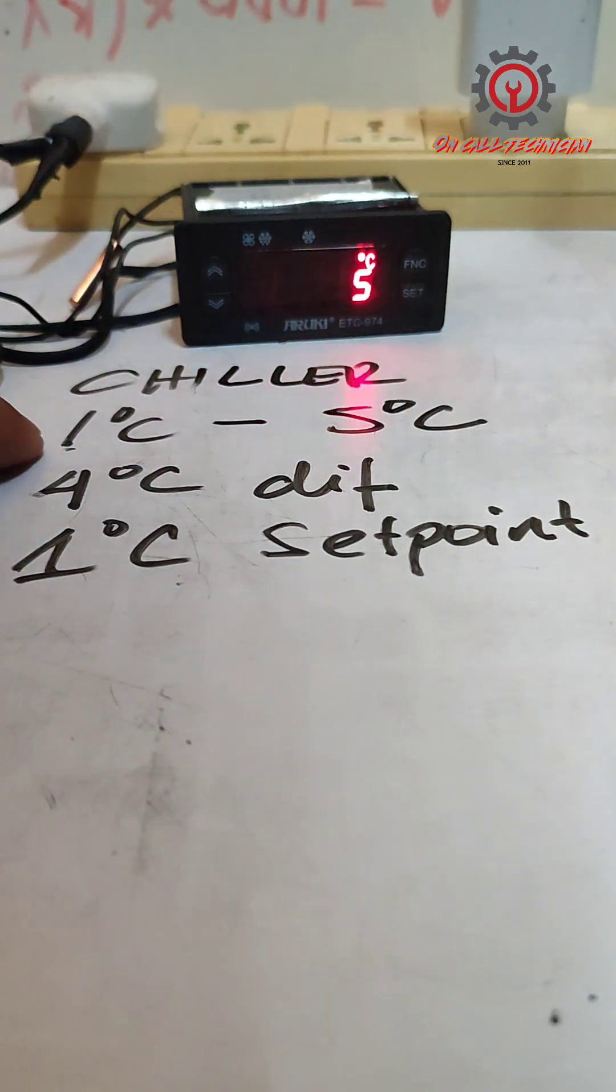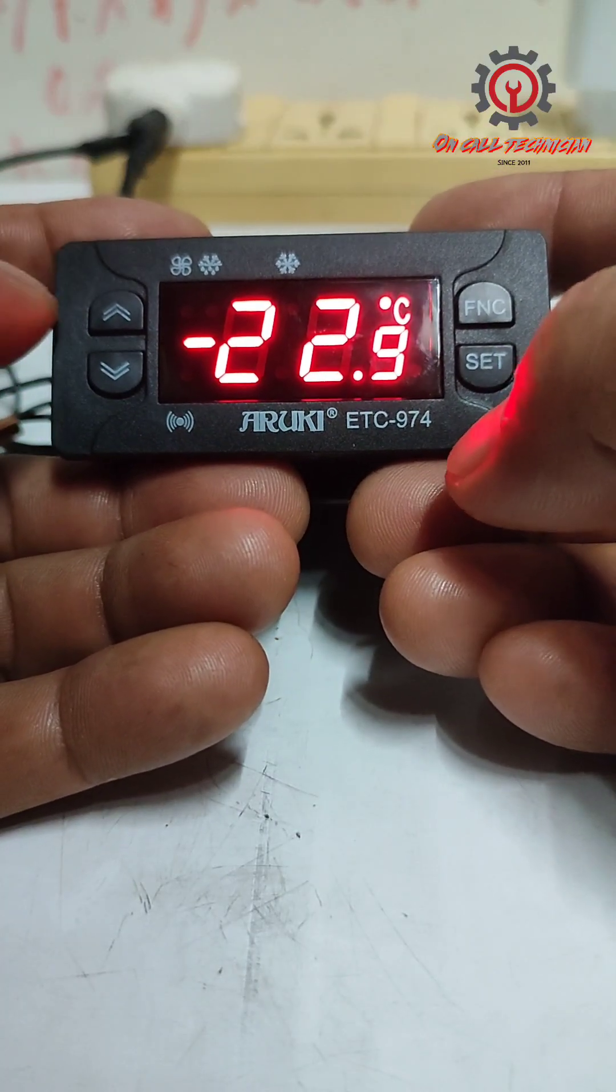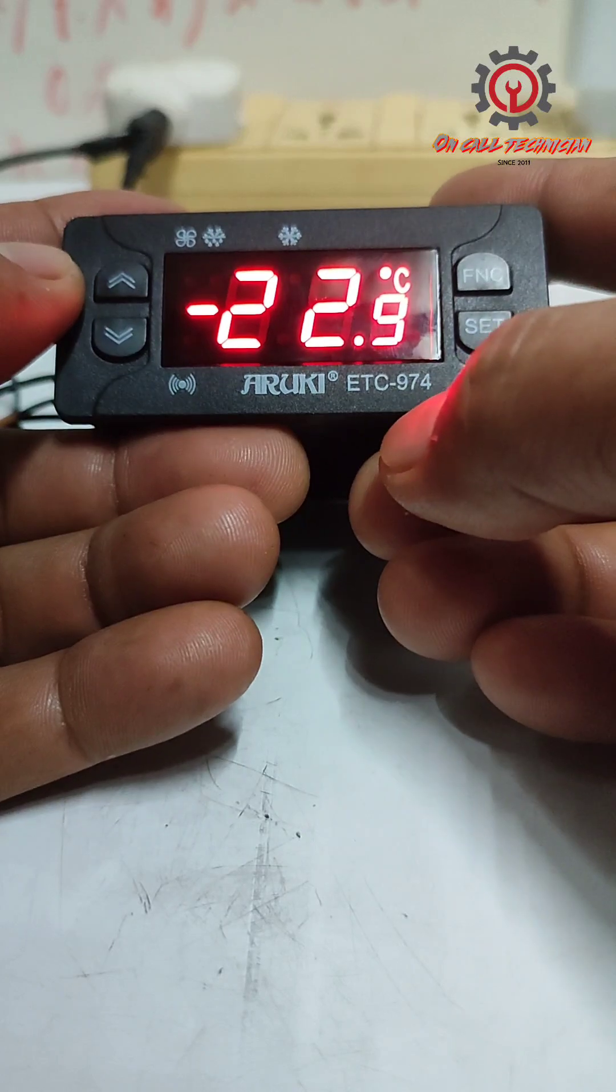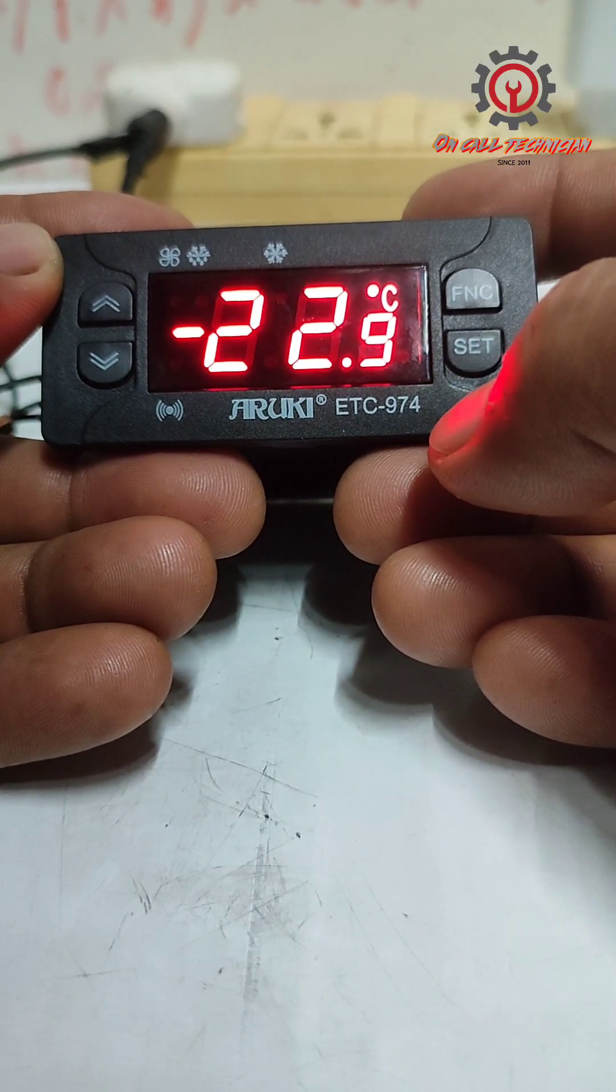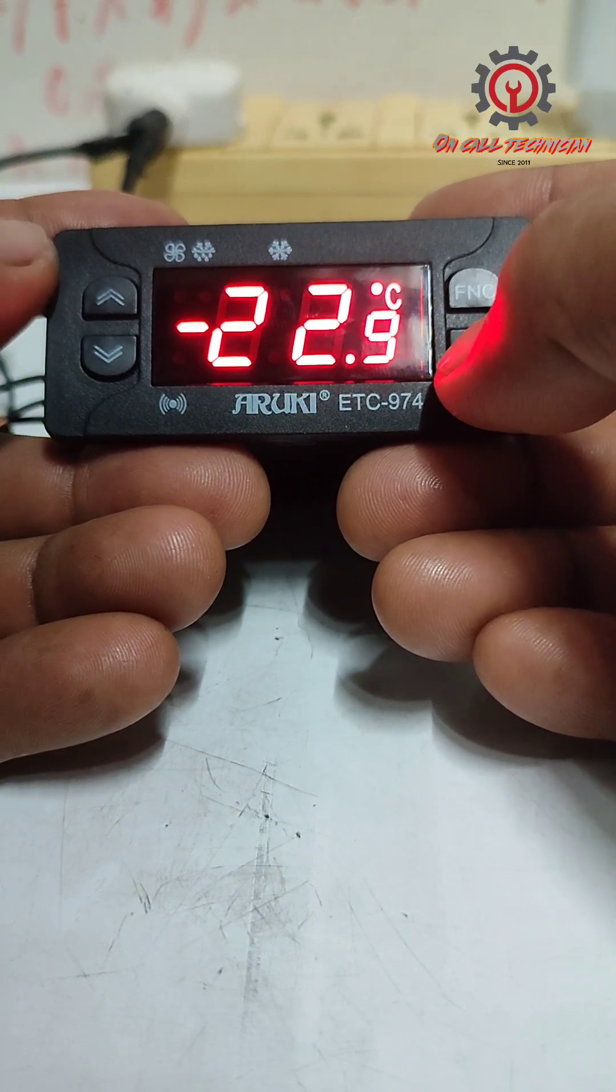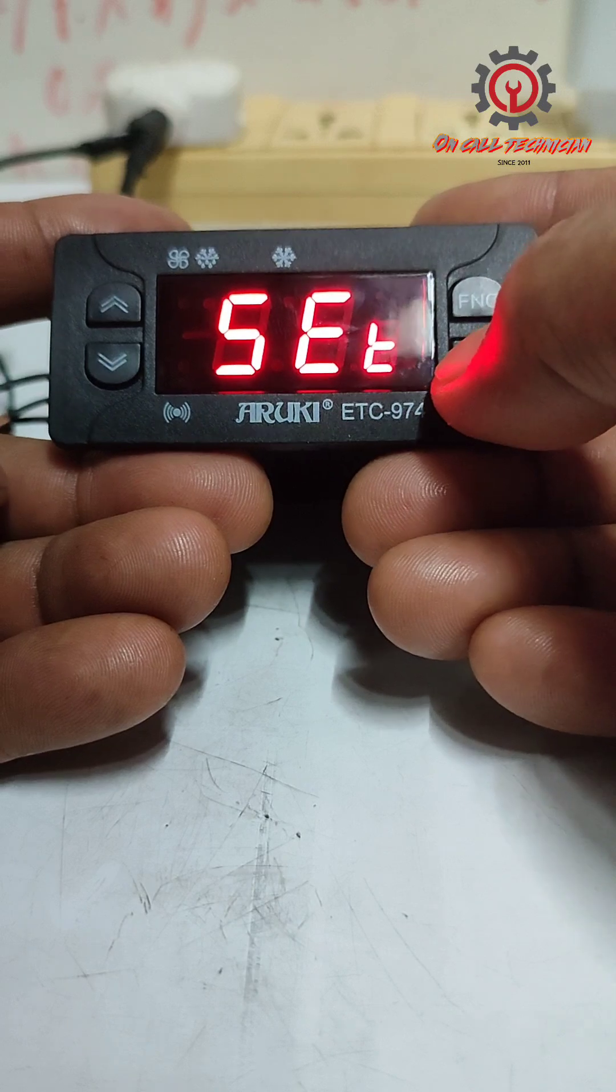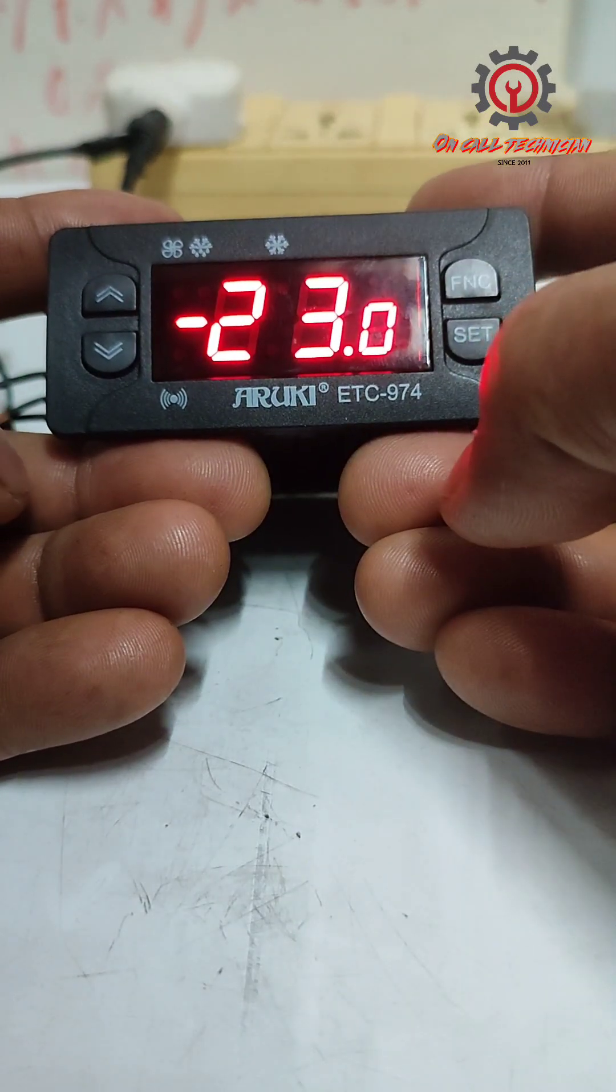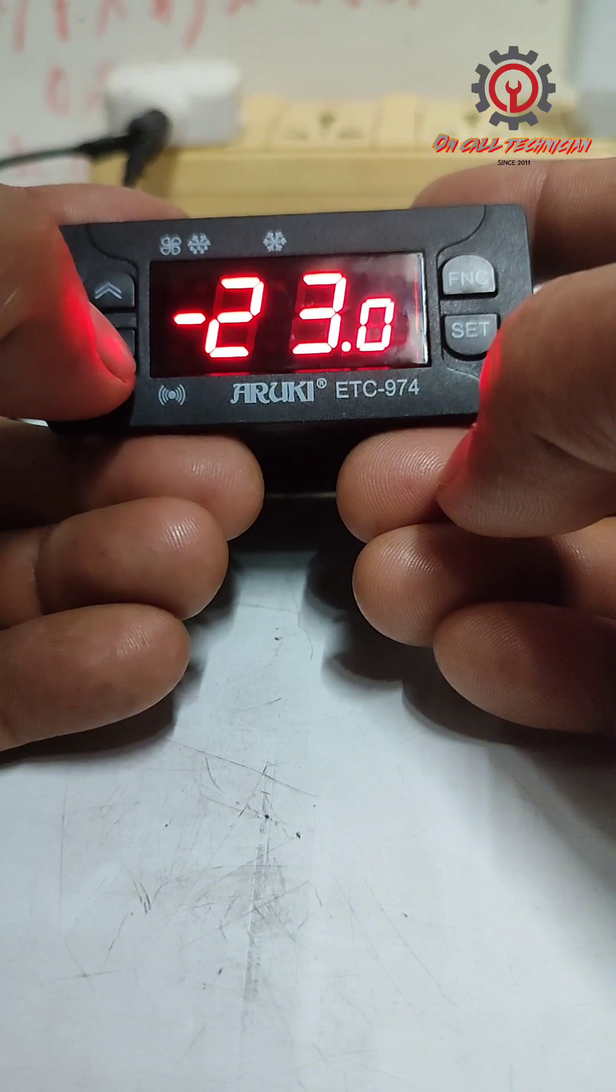There it is, it's off. How to change the set point of ARUKI ETC-974 into chiller setting? To do that, just press the set button here, and then press set again. We're going to change negative 23 into positive one.